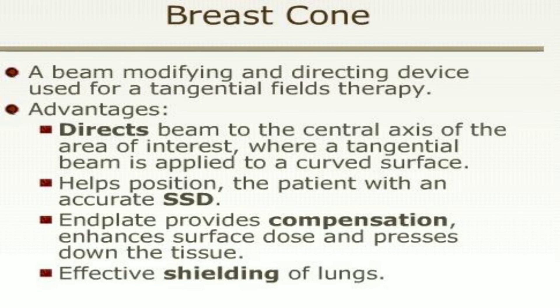A breast cone is a beam-modifying and directing device used for tangential field therapy. Advantages include: it directs the beam to the central axis of the area of interest where a tangential beam is applied to a curved surface; it helps position the patient with accurate SSD; the end plate provides compensation, enhances surface dose, and presses down the tissue; and it provides effective shielding of lungs.